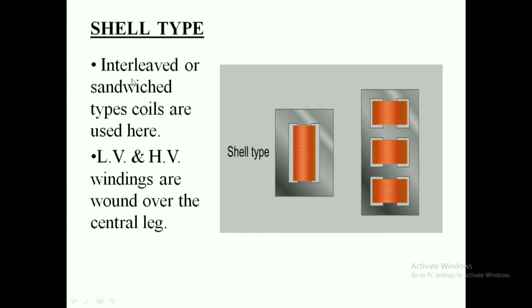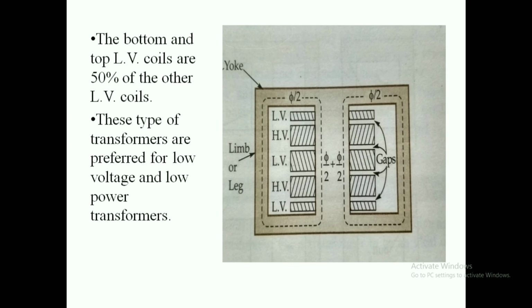In shell type of transformer, interleaved or sandwich type or disc type windings are used. The low voltage and high voltage overall winding is placed over the central leg in case of shell type of transformer. And how the low voltage and high voltage windings are placed, we have to see in the intersection view of this type of transformer. This is the intersection view.